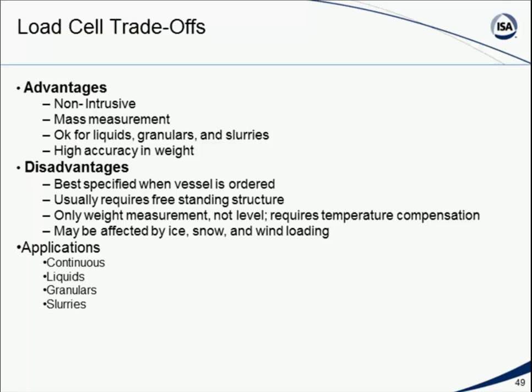But again, it's something that really is hard to add on later. If you're going to use this approach, then before you order a vessel and manufacture it and have it put in place, you really want it there. Again, it usually requires some kind of either a freestanding or free-hanging structure. You can't put a load cell on something that's already mounted in place. It's got to be sitting on the load cell. So the structure has to be freestanding, and that means that the structure better not be affected by outside forces. So if it's a tank outside, wind loading will affect it. If it gets covered with snow or ice or just wetted down by rain, that will affect its measurement. Now again, it's an overall weight measurement, so if you have something in the tank like a fluid whose density will change over temperature, well, then we're not really measuring the level in the tank. So if stuff in the tank gets hotter and therefore expands, we're not going to see a difference because the weight hasn't changed.